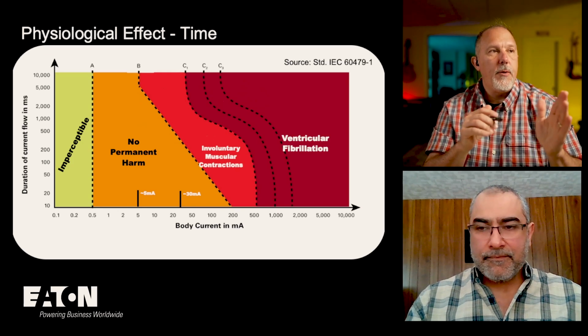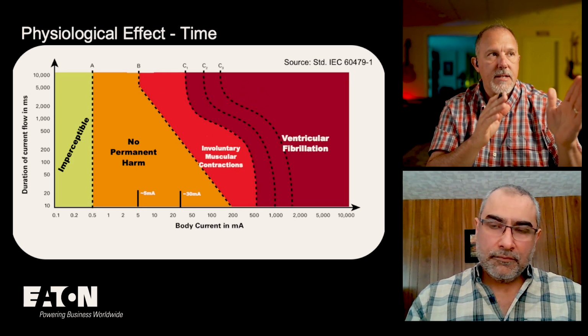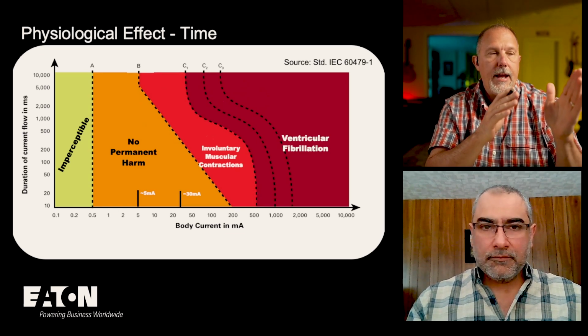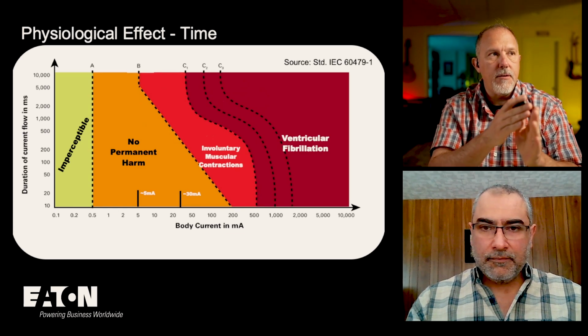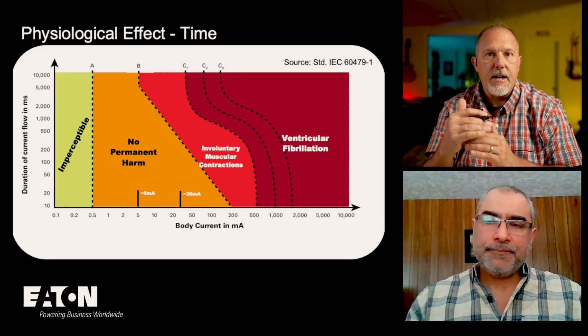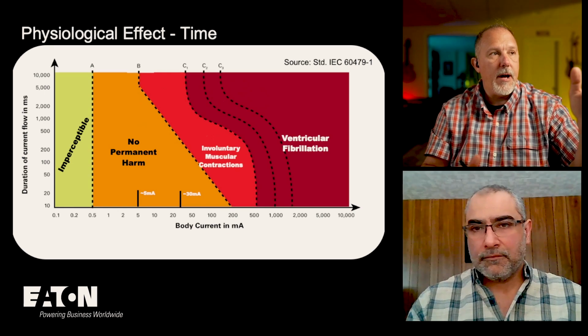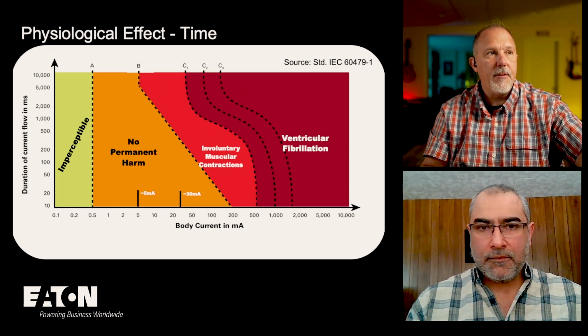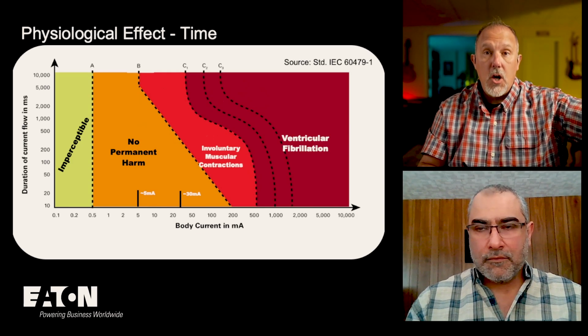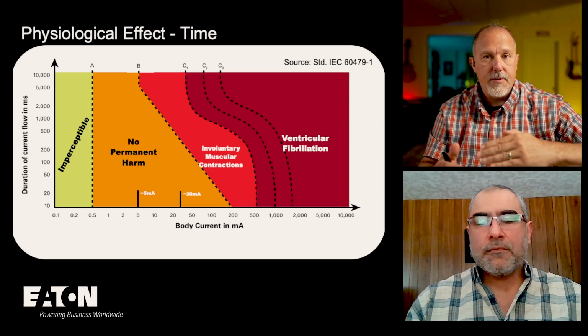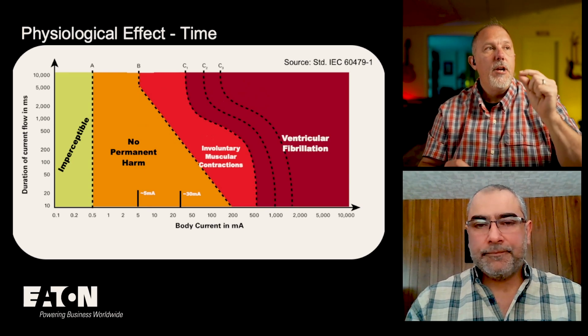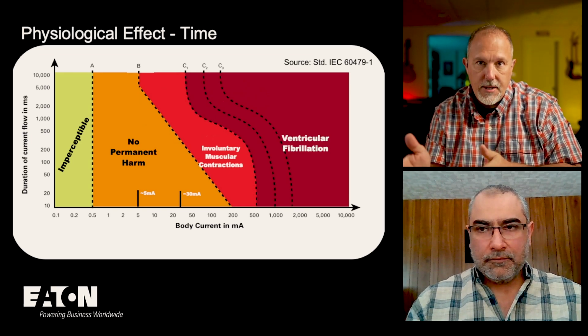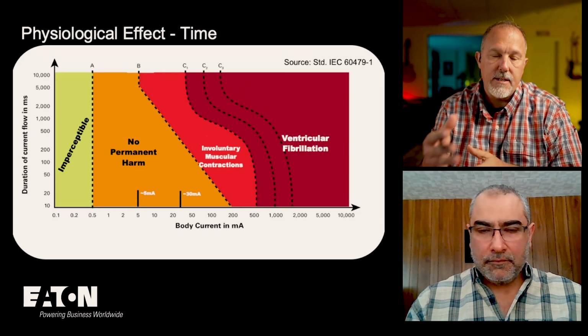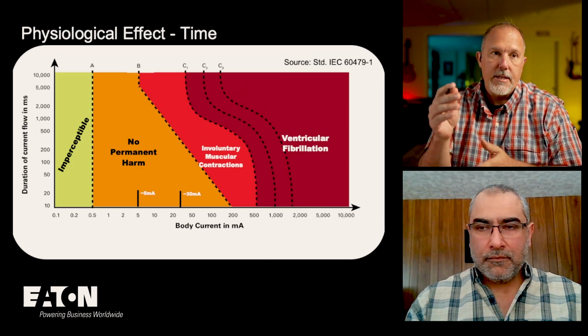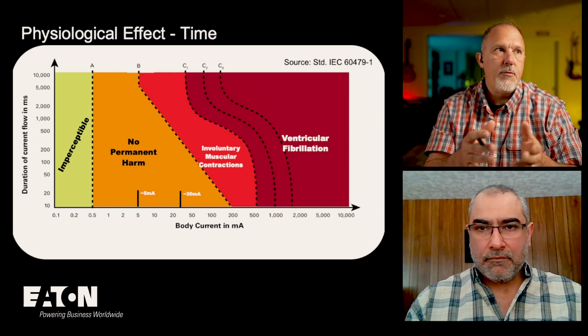Yeah. So you have basically a damage curve for the human body, and for higher values of current, shorter values of time are permitted. And to your point, I get into the involuntary muscular contractions somewhere above 5 milliamps for a longer period of time, but as current goes up, that time period comes down, makes it shorter. So the difference between that European RCD type of device is it doesn't have the opening time to prevent let go, right?